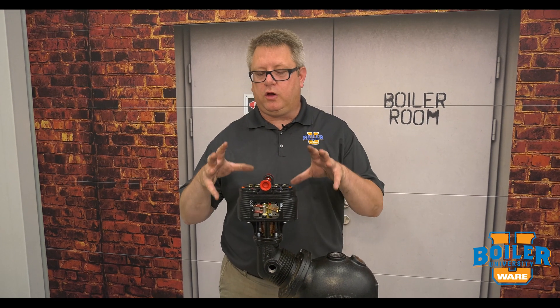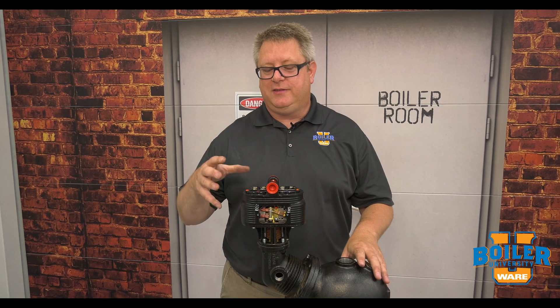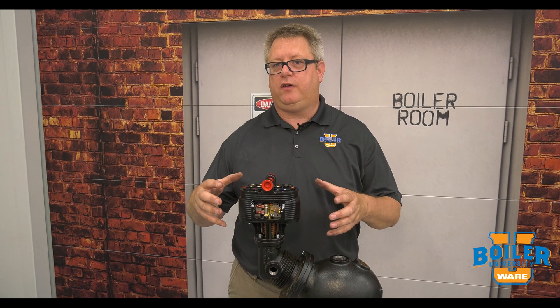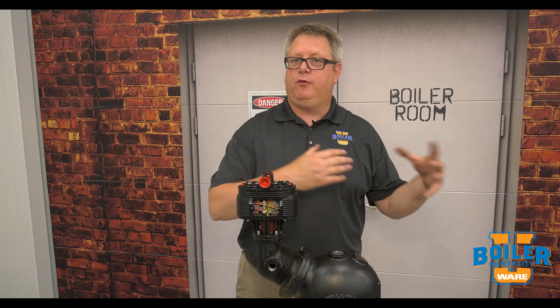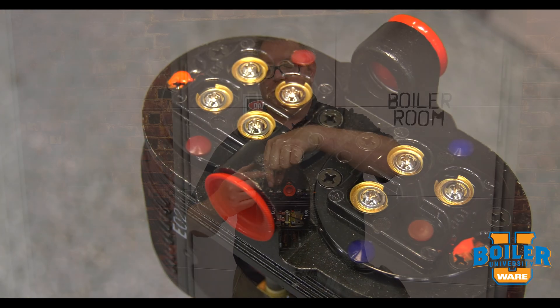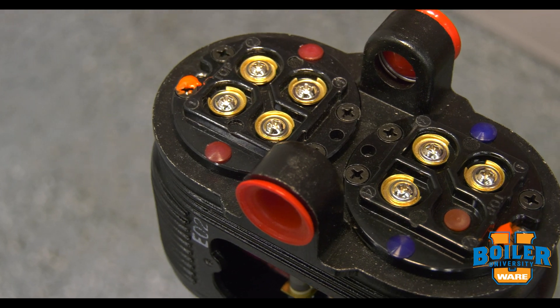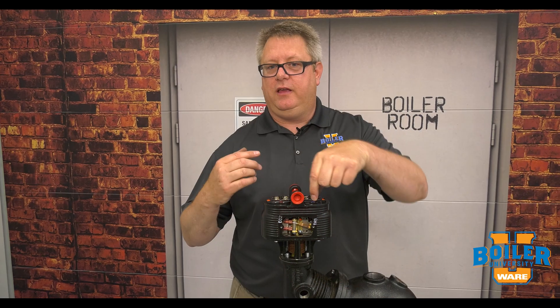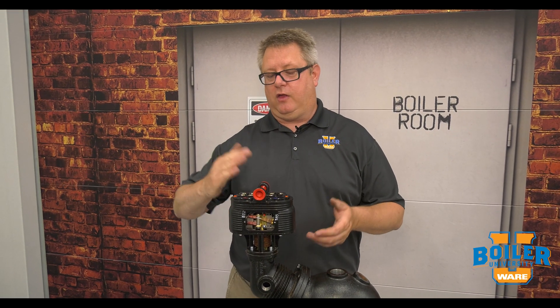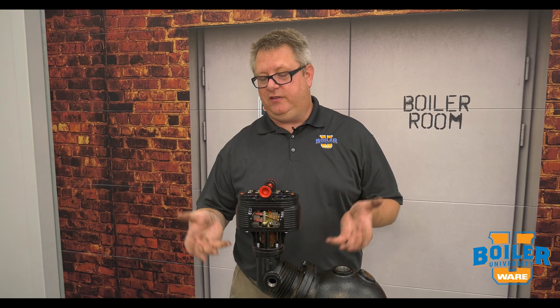On this week's Boiler Tip, we're going to look at the McDonnell Miller 7B switch for the 93-94 head series. The big change with the 7B switch from all the other 93-94 switches is that we've got a standard make or break switch for the burner circuit, but the water side circuit is a modulating circuit — a slide wire circuit. That's referred to as a slide wire potentiometer, a Series 90.